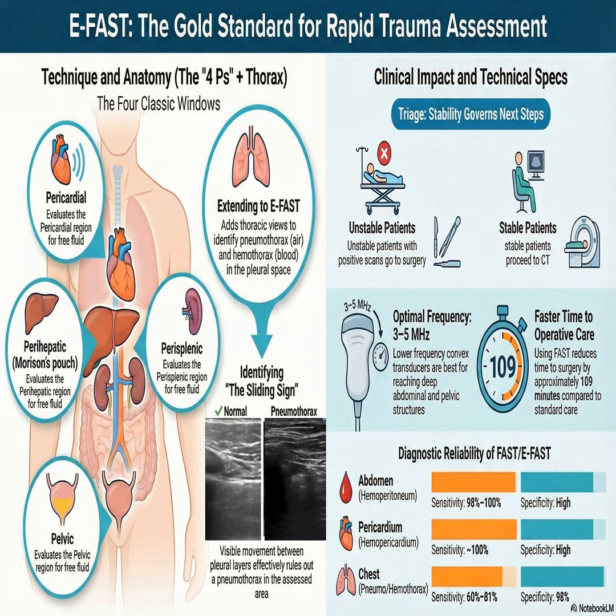Right. If you crank the overall gain, the entire screen just washes out in white noise, completely obscuring subtle anechoic fluid collections. That is where time gain compensation, or TGC, becomes essential. Sound waves lose energy as they travel deeper into the body due to attenuation. So the echoes returning from a deep structure, like the posterior aspect of the liver, will naturally be weaker than echoes returning from the anterior abdominal wall. So if you rely solely on overall gain, the superficial tissues will be blindingly white while the deep tissues remain completely dark.